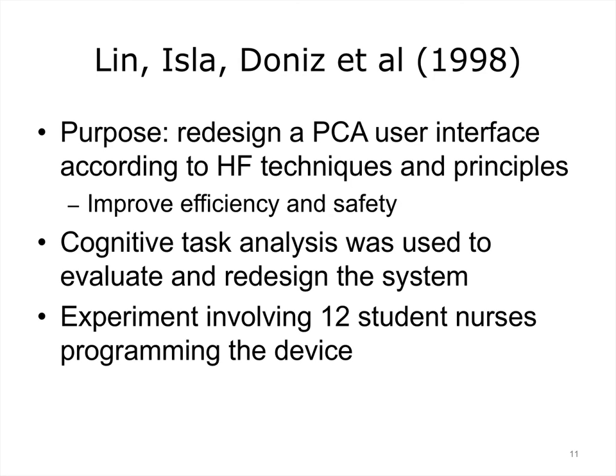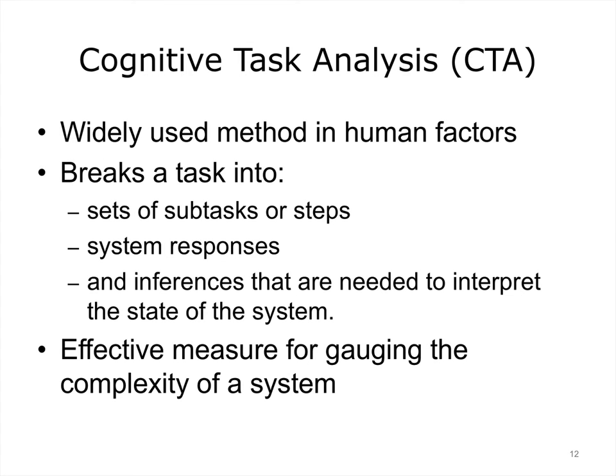Lin and colleagues investigated the effects of two interfaces to a commonly used PCA device, including the original interface. Based on a cognitive task analysis, they redesigned the original interface so that it was more in line with sound human factors principles. Cognitive task analysis is a widely used method in human factors. It breaks a task into sets of subtasks or steps, system responses such as changes in the display as a result of an action, and inferences needed to interpret the state of the system. It is an effective measure for gauging the complexity of a system.